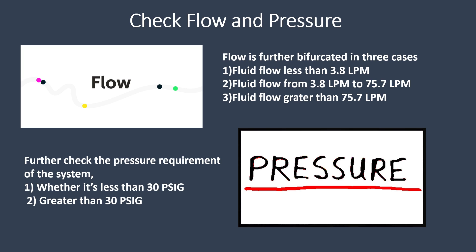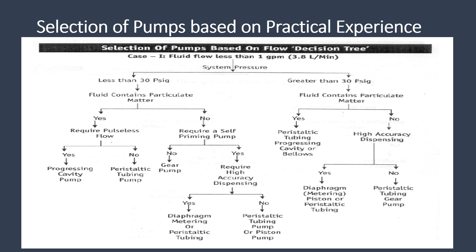For example, for fluid flow less than 3.8 lpm, check the selection as per decision tree Case 1. If system pressure is less than 30 psig, further check for particulate matter in the fluid. If the fluid contains particulate matter and requires pulse-less flow, select a progressing cavity pump; if pulse-less flow is not required, select a peristaltic tubing pump, commonly used in pharmaceuticals. If the fluid does not contain particulate matter, options include gear pump and diaphragm pump. Further selection is based on priming and accuracy. For pressure greater than 30 psig, pump selection is based on particulate matter and accuracy.